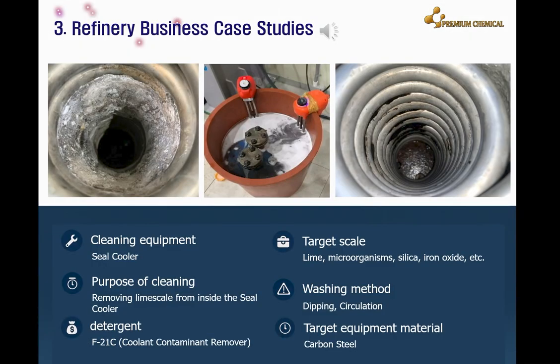The next business case we'll cover is a seal cooler, which protects and cools the seals of pump motors used in refineries when they rotate. When a seal rotates, temperatures can reach localized temperatures exceeding 300 degrees Celsius. The device that cools these seals is called a seal cooler. Calcium solidifies in the gaps between the tube coils of the seal cooler, forming a rock-like hardness. It's so hard that it can't be broken even with a hammer. This rock-hard scale can be easily removed through chemical cleaning, while the seal cooler is connected to the pipes.